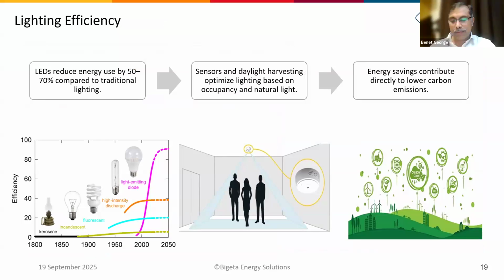Now, in all these cases, we have to remember two things. You can reduce your energy consumption mainly in two ways. One, by improving the efficiency of the system. Second, by improving the efficiency of the operation. For example, in this case, you can see the efficiency of lamps increasing from, say, incandescent to fluorescent, to high intensity lamps, and finally to LED lamps. When you talk about efficiency of the system here, it is lumen per watt: how much light it is producing per watt given to that bulb.